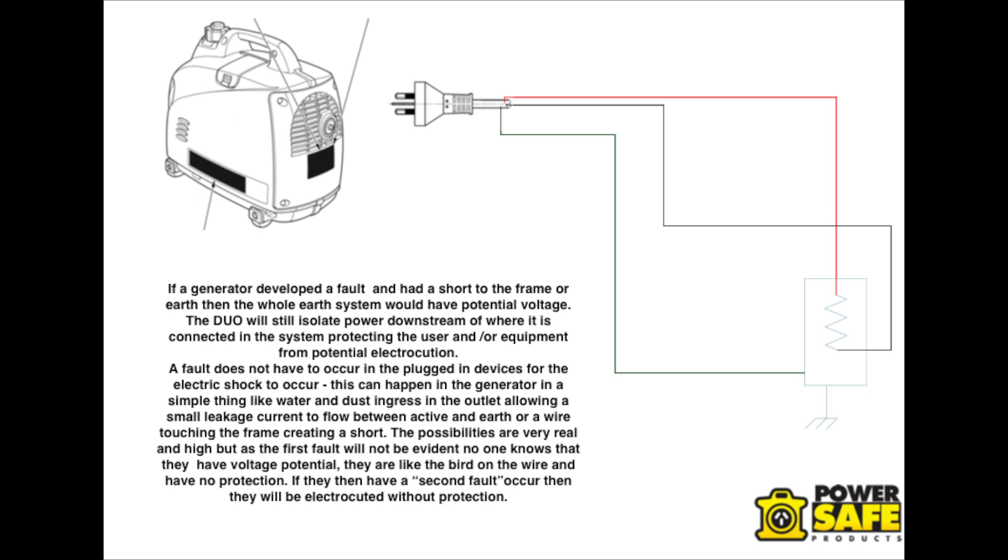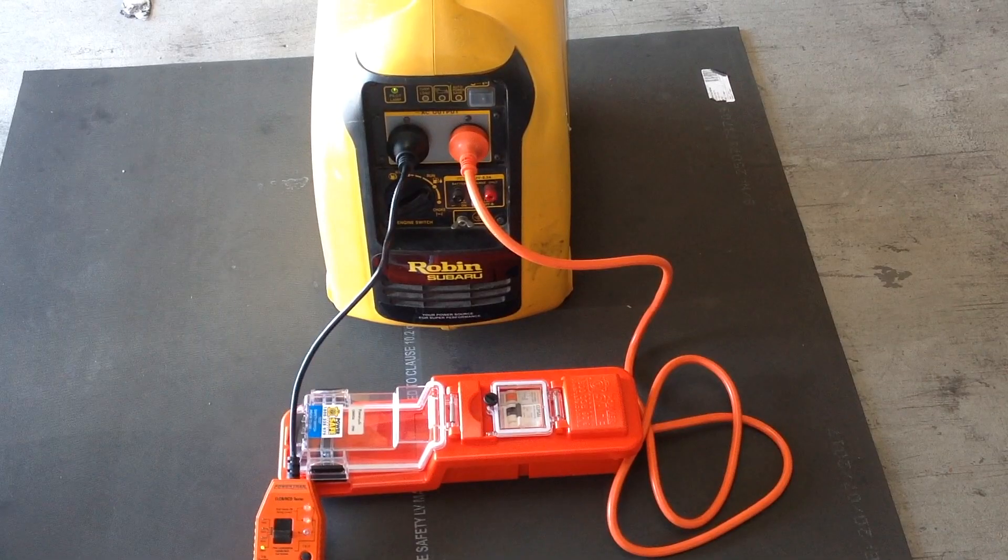The DUO also protects the user by shutting the power off if the fault does not occur in the devices attached to the outlet. In the event that the fault occurs inside the generator or in a different circuit, the DUO will isolate the circuits that are attached to it to protect the user using the appliances downstream of the DUO.